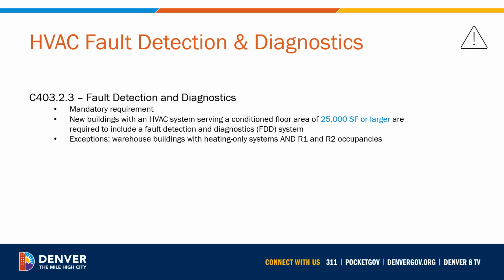HVAC fault detection and diagnostics is a new mandatory requirement for new buildings with an HVAC system serving a conditioned floor area of 25,000 square feet or greater. Systems that are exempt include those serving warehouse buildings with heating-only systems and those serving R1 or R2 occupancies. An example of a system where fault detection and diagnostics is required would be an air handling unit serving areas of an office building totaling to more than 25,000 square feet.